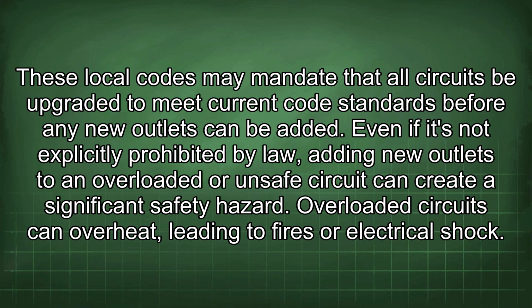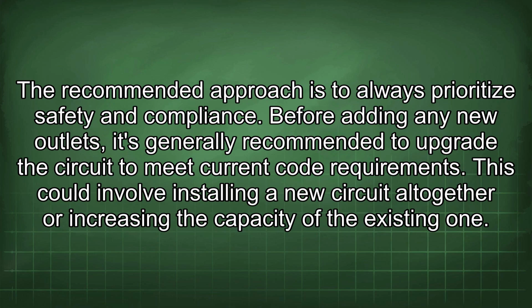Overloaded circuits can overheat, leading to fires or electrical shock. The recommended approach is to always prioritize safety and compliance. Before adding any new outlets, it's generally recommended to upgrade the circuit to meet current code requirements. This could involve installing a new circuit altogether or increasing the capacity of the existing one.